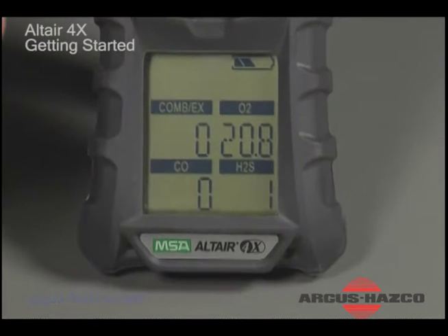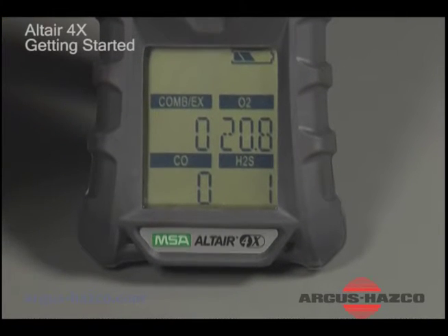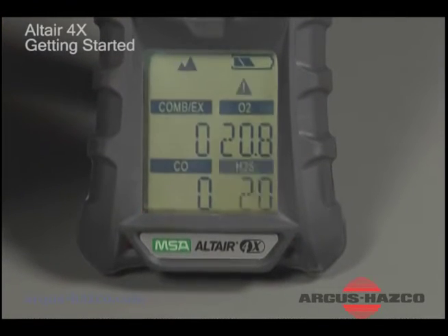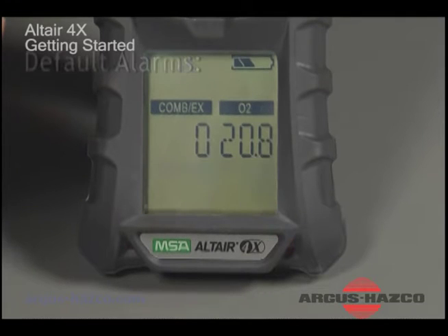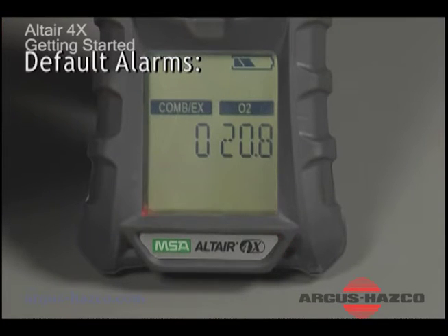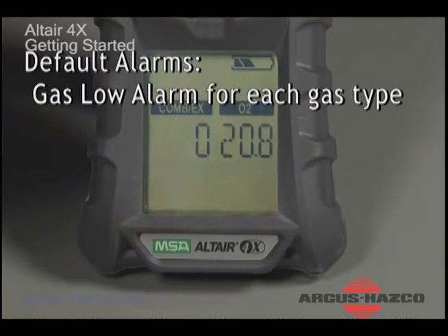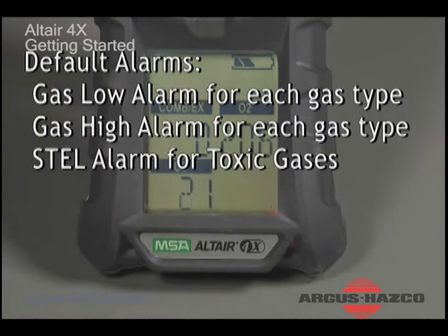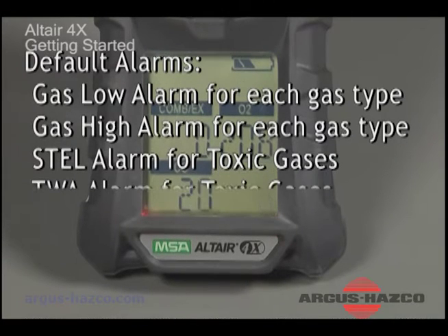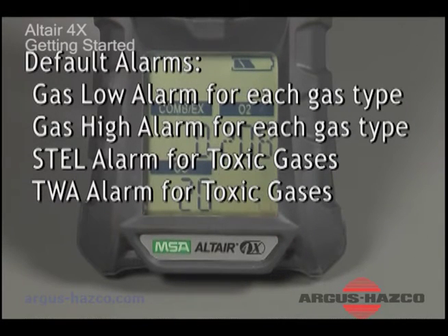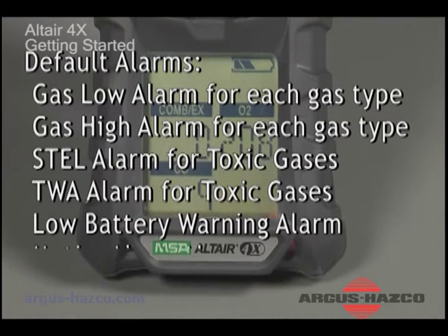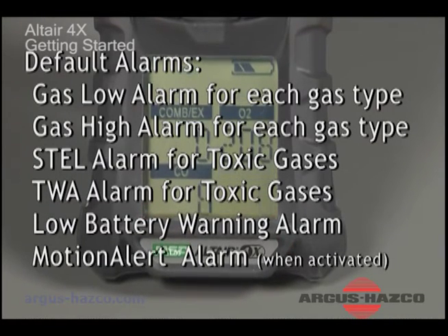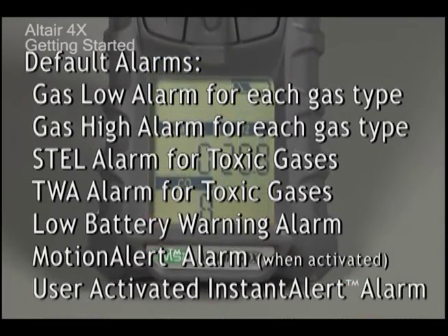While in measure mode, several alarm states exist to alert users to various potentially hazardous situations. The instrument's default alarms are: gas low alarm for each gas type, gas high alarm for each gas type, STEL or short-term exposure limit alarm for toxic gases, TWA or time-weighted average alarm for toxic gases, low battery warning alarm, motion alert alarm when activated, and user-activated instant alert alarm.